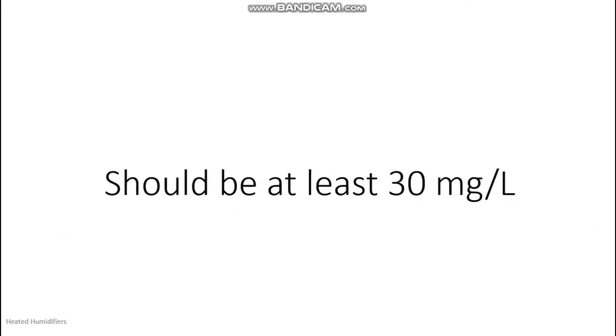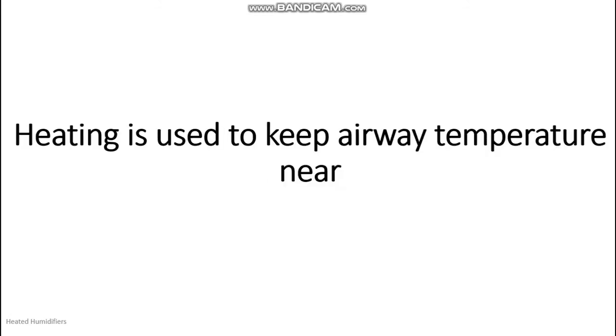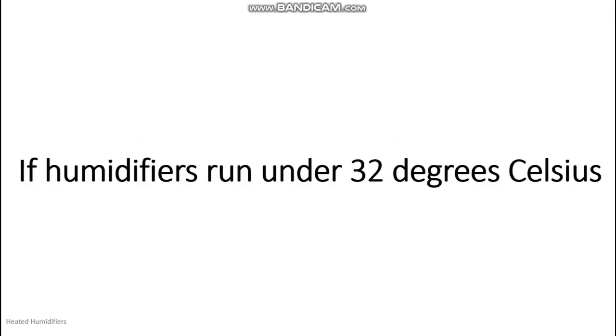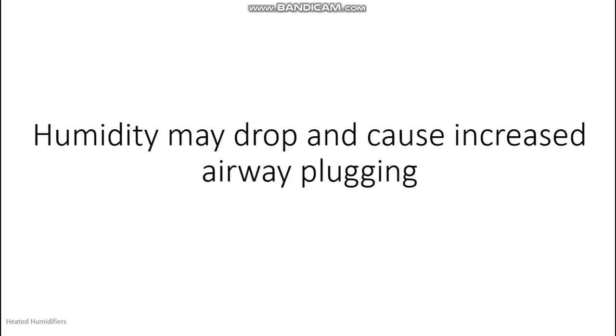Humidity levels for intubated patients should be at least 30 mg per liter. Heating is used to keep airway temperature near 35 to 37 degrees Celsius. If humidifiers run under 32 degrees Celsius, humidity may drop and cause increased airway plugging.